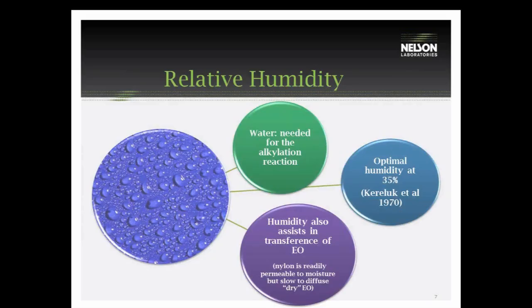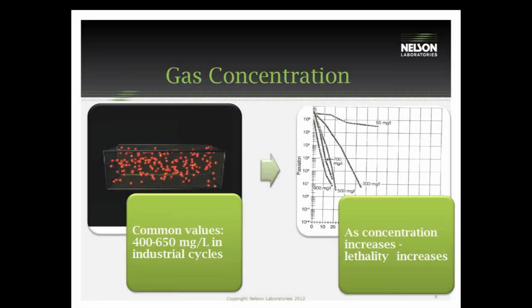Relative humidity is needed for sterilization for the alkylation process. The optimal humidity level is about 30 to 35 percent. Anything in excess of that is going to increase the rate of sterilization and increase that alkylation reaction. Gas concentration is another variable. Common values for gas concentration are 400 to 600 milligrams per liter. As you increase the concentration of ethylene oxide, you will also increase the lethality rate of the process.